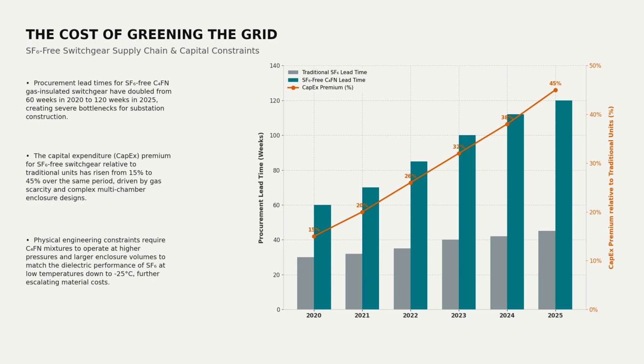These cost increases are driven by fundamental physical differences between the gases. C4-FN has lower low-temperature performance than sulfur hexafluoride. To compensate, equipment manufacturers must design larger, high-pressure multi-chamber enclosures. This increases the volume of specialized aluminum and steel required per unit. The physical reality of chemical substitution is inflating the cost of grid decarbonization.